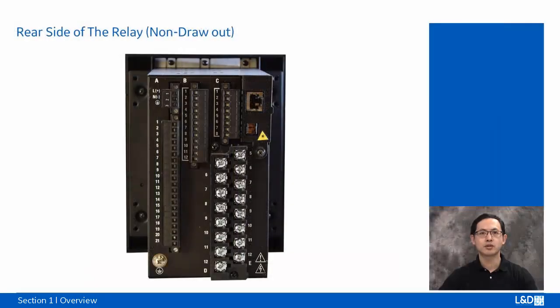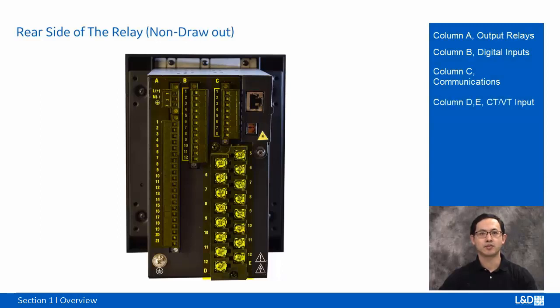For the non-drawout type relay, column A is for output relays. Column B is for digital inputs. Column C is for communications. Columns D, E are for the CT, VT inputs.